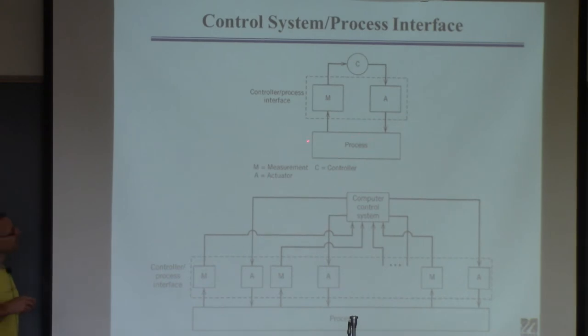When I show you a picture like this, I hope you appreciate that this thermocouple is not floating around in the liquid. You don't just hang a thermocouple in there with a mixer, right, and it gets wrapped around there. We'll talk about it. It's a little thermal well that sits on the side of the reactor and contacts the fluid, usually through the material of construction of the valve. It's not just floating around. So your ability to control is going to depend on how well you can measure things and usually if your valves are working. And in this idealistic world of academia and the undergraduate curriculum, you may think this always works, but in reality, this never works. If you're in a plant and you ask some guy, do all your sensors and all your valves work, the answer is, of course not. Most of them do, most of the time, but some of them work all the time, and a few of them almost never work. So this is important for practical applications of control, so we at least want to touch on it. So these are very simple pictures. What does it say? They call this the control system process interface. So you've got a process. This means a plant. The plant's outside. It's hot. You're usually in a fairly undesirable location, including places like Texas and Louisiana.